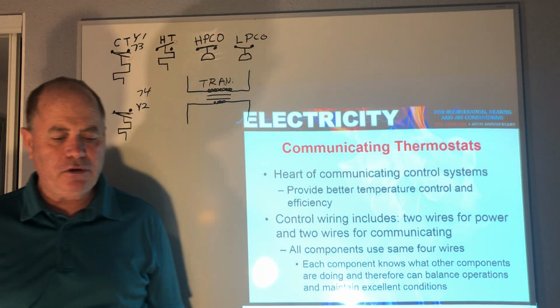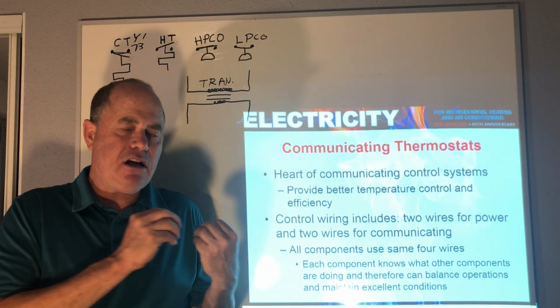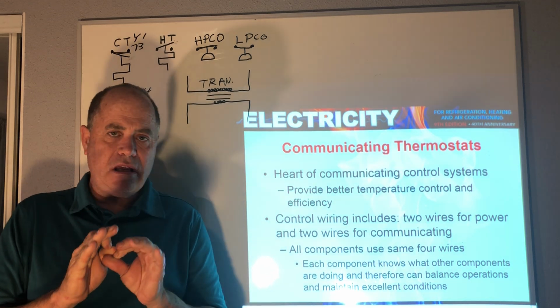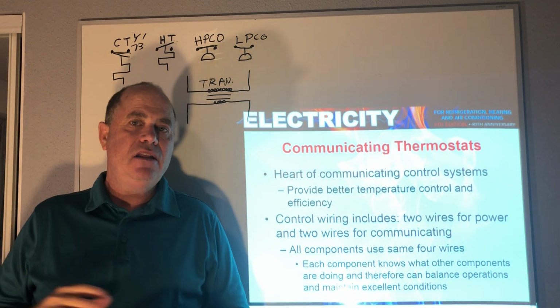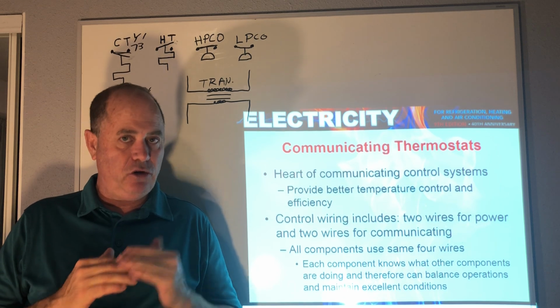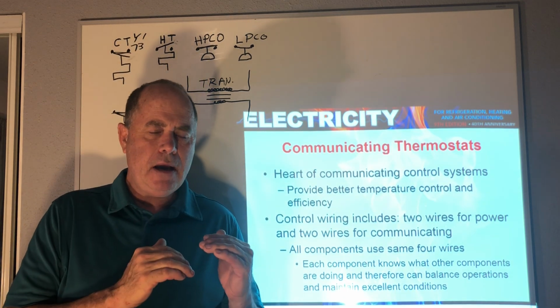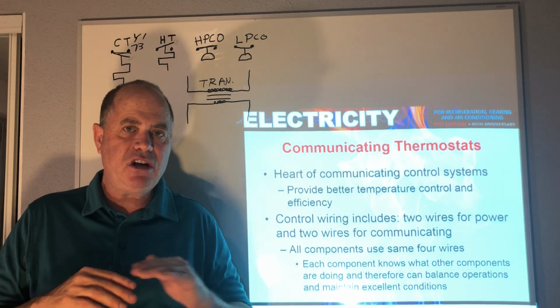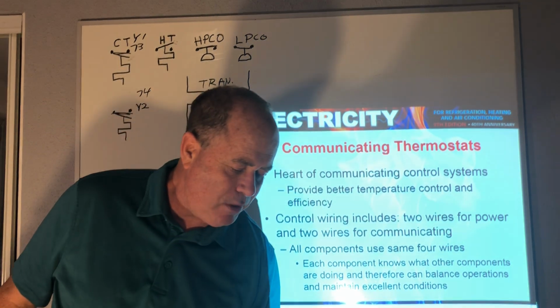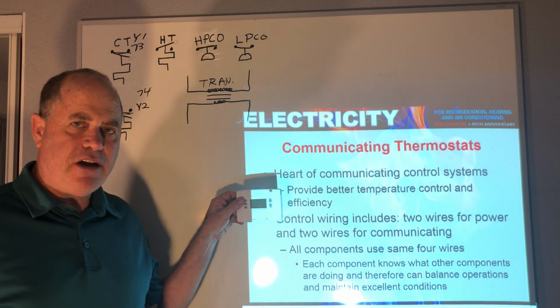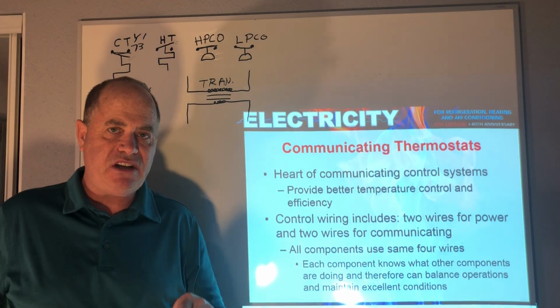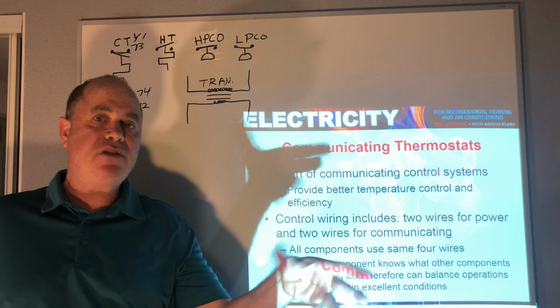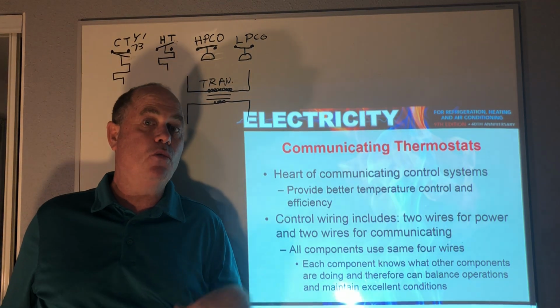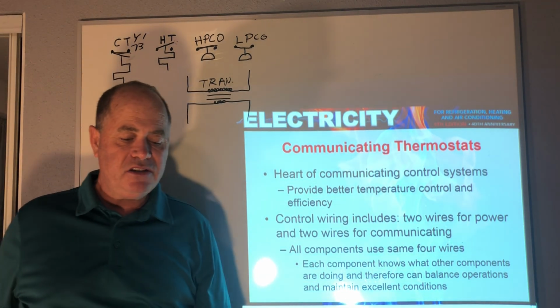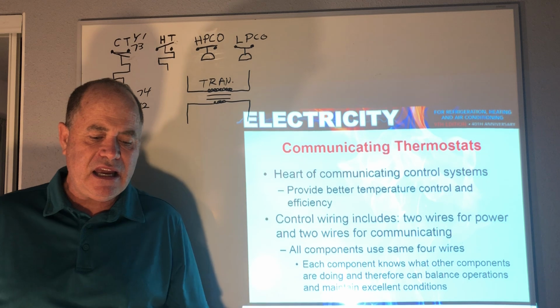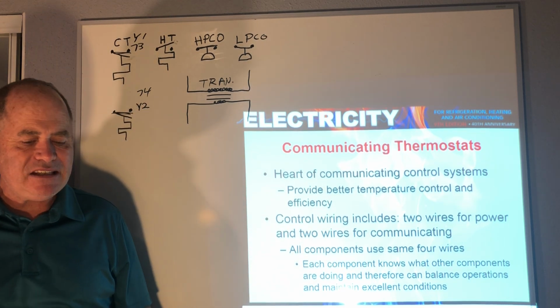Okay, now communicating thermostats, again, now I'm going to talk a little more modern than this slide. With communicating thermostats in energy management, this is where you usually have a signal of 0 to 10 volts DC or 0 to 20 milliamps, and we use this communication signal. And a lot of times what we have on the wall, the actual definition isn't really a thermostat, it's just a temperature sensor that's reporting to a circuit board that makes the decisions whether to bring on more cooling or less cooling or whatever. So in these communicating thermostats, they're communicating as part of a bigger system.